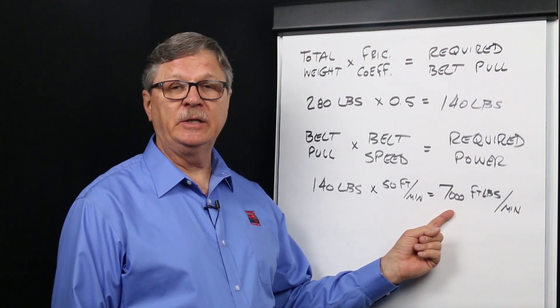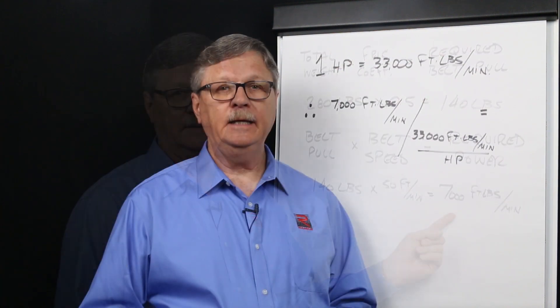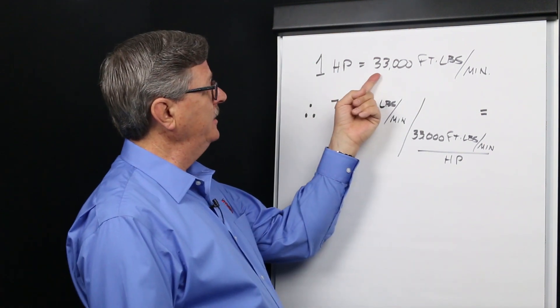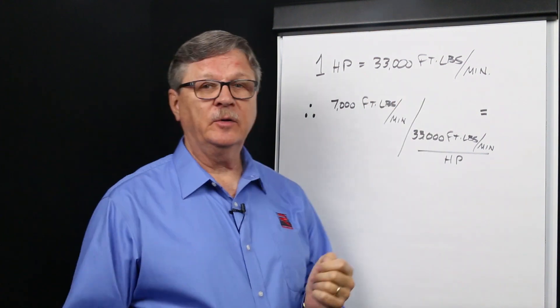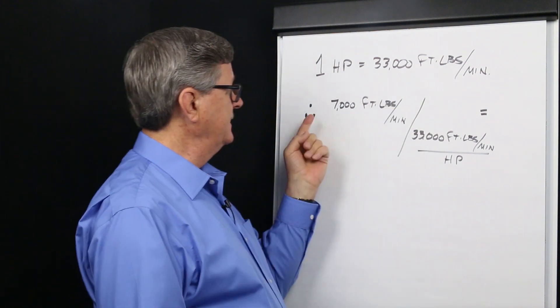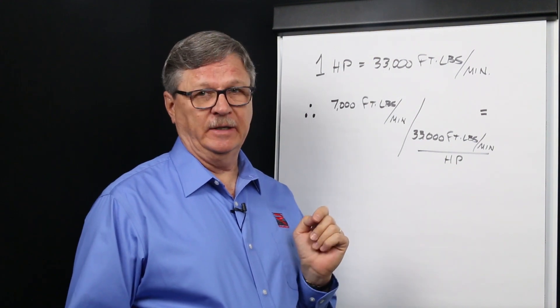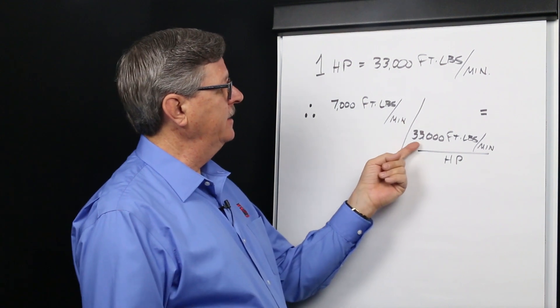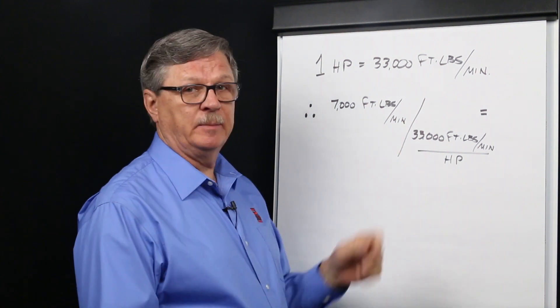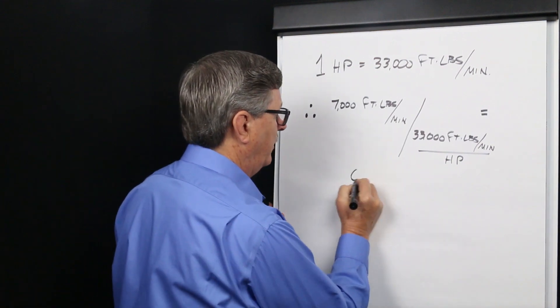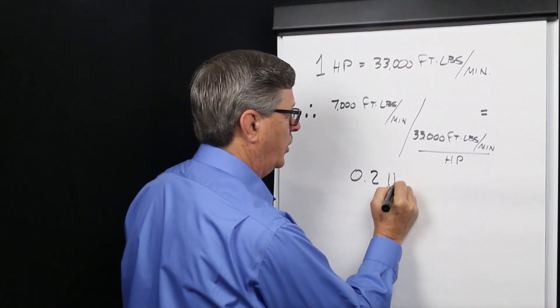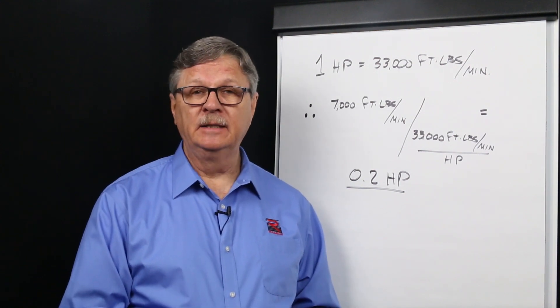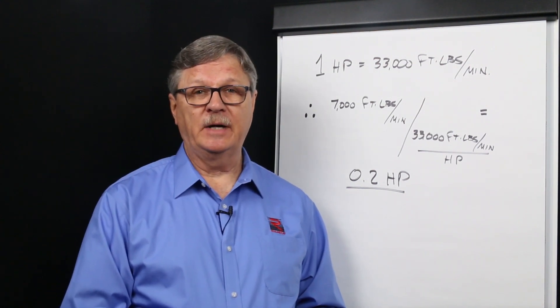We can now convert that to a useful unit. In imperial units, we know that one horsepower equals 33,000 foot-pounds per minute. Therefore, our power requirement of 7,000 foot-pounds per minute can be converted using this equation. 7,000 foot-pounds per minute divided by 33,000 foot-pounds per minute per horsepower equals a power requirement of 0.21 horsepower.